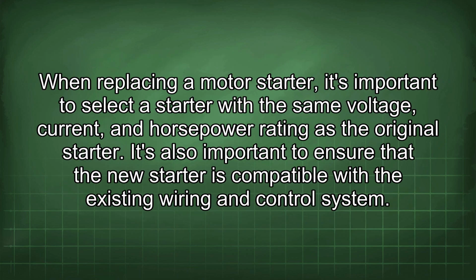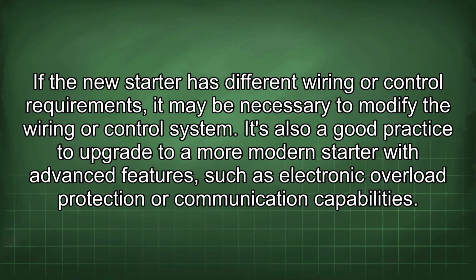When replacing a motor starter, it's important to select a starter with the same voltage, current, and horsepower rating as the original starter. It's also important to ensure that the new starter is compatible with the existing wiring and control system. If the new starter has different wiring or control requirements, it may be necessary to modify the wiring or control system. It's also a good practice to upgrade to a more modern starter with advanced features such as electronic overload protection or communication capabilities.